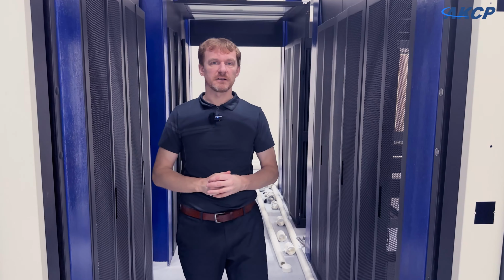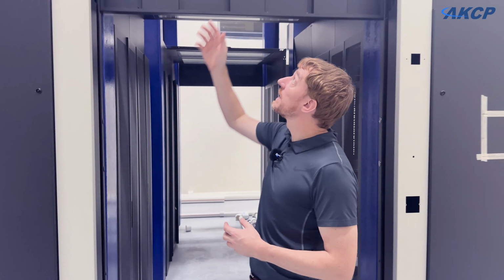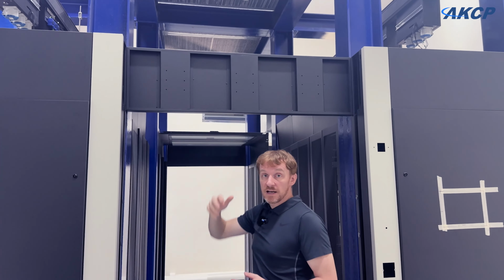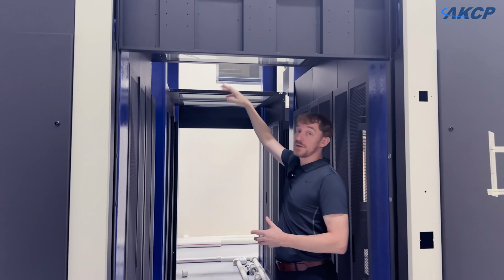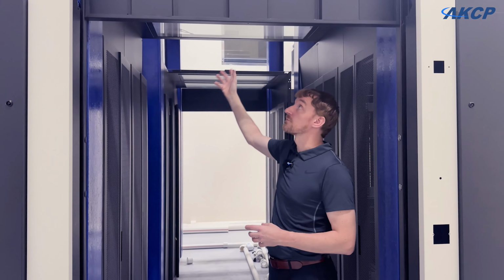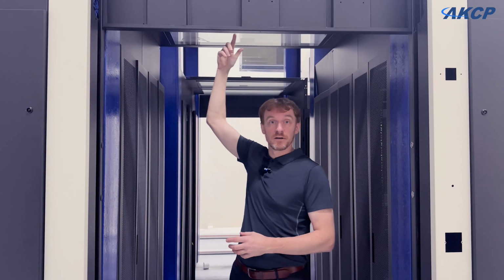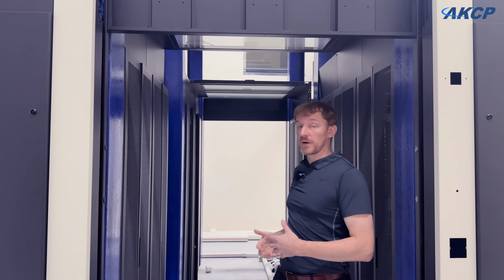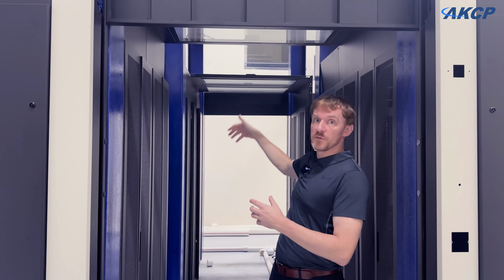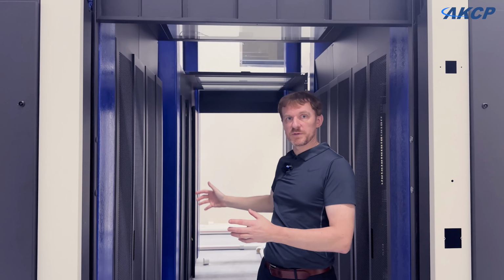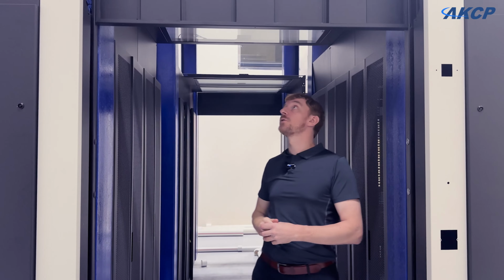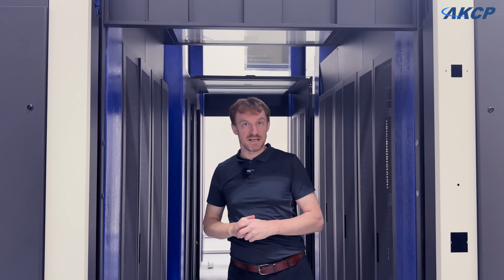So here we are in our hot aisle containment in hall number 1 of the test data center. And what you've just seen is the overhead heat exchangers being hoisted up into place. Above me here, we have these overhead heat exchangers. There will be a chimney built around these. The concept here is that we can open up the containment ceiling and allow the hot air to rise. It'll go through those heat exchangers and be cooled down. So they can function like an in-row AHU, but we've moved it on top of the containment so it frees up some space. So that's one method of cooling, and that's why we've lifted those overhead heat exchangers up there.